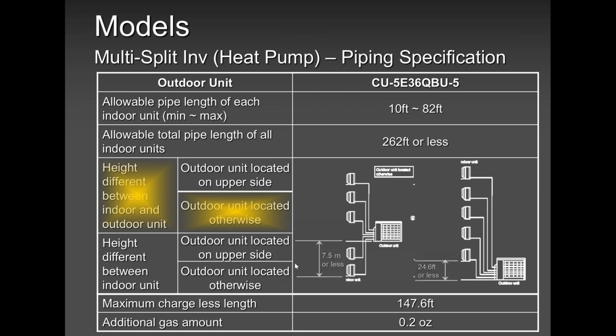When I'm installing a multi-zone, I like this design because each and every indoor unit is kind of in an average spot. It's kind of getting an average pipeline. I don't like this kind of application, but if you have to, you have no choice, no problem. But again, from a technical point of view, the outdoor unit will have to work super hard for this unit to get optimum cooling or heating. So in my case, I always look for a sweet, soft spot to place this outdoor unit so it doesn't have to struggle that much.